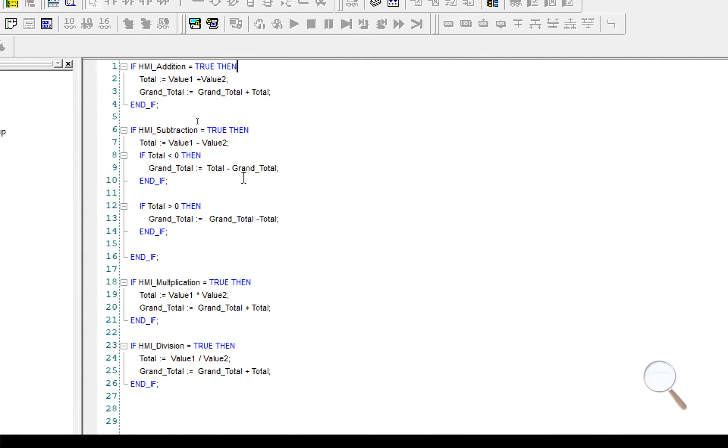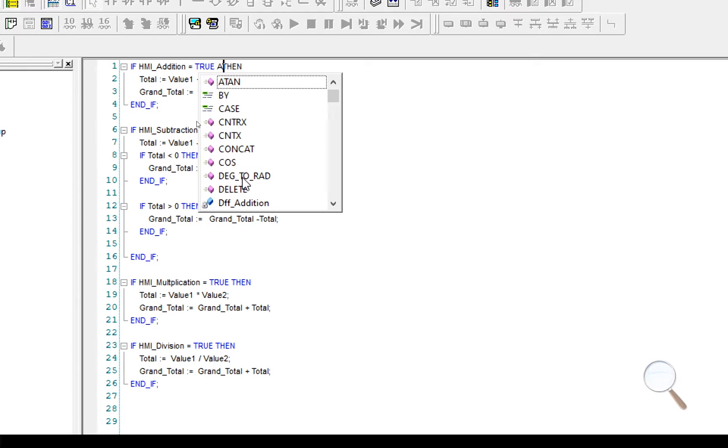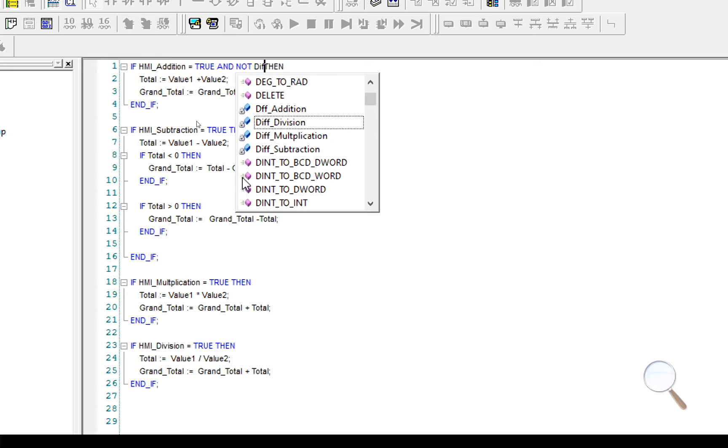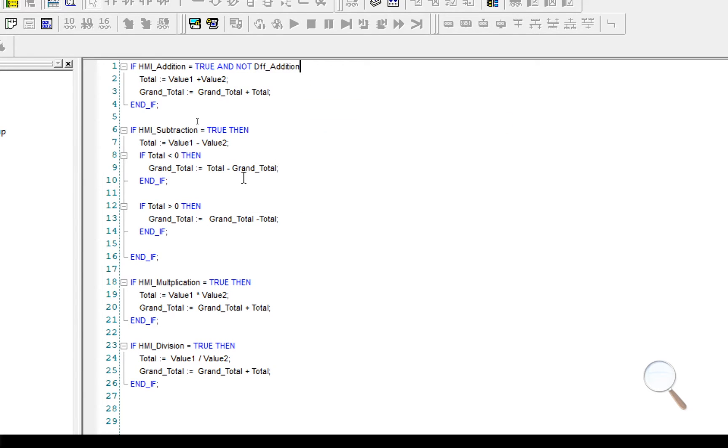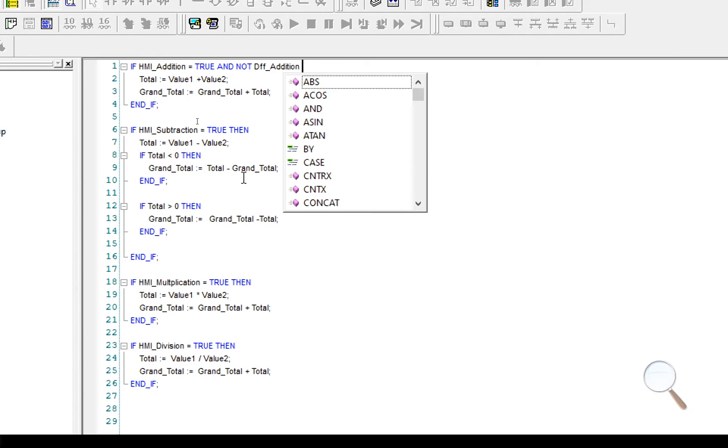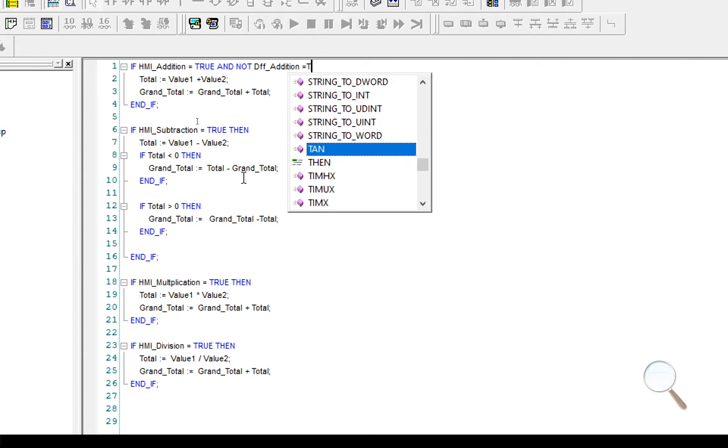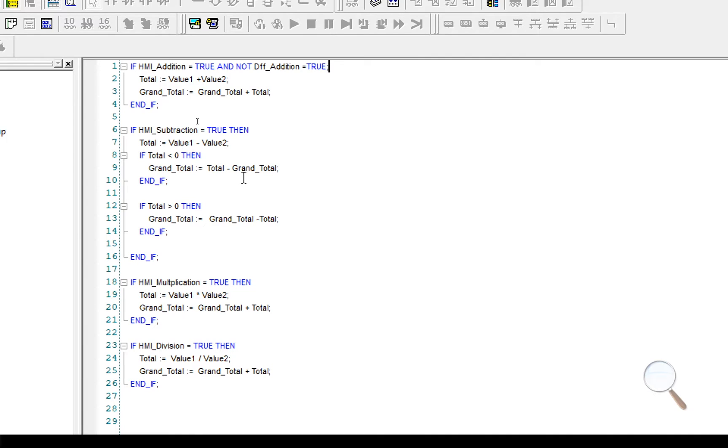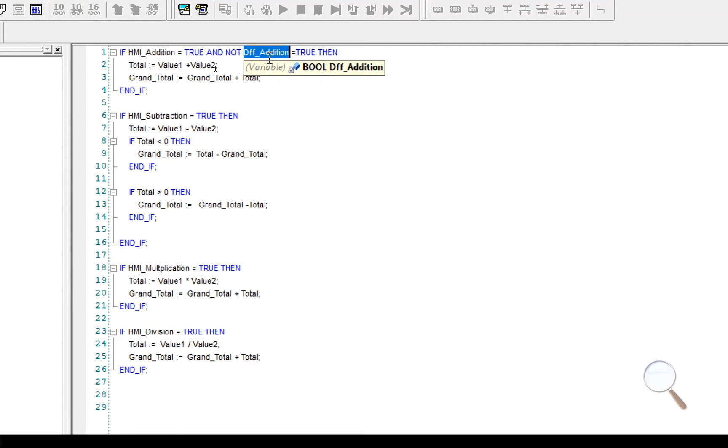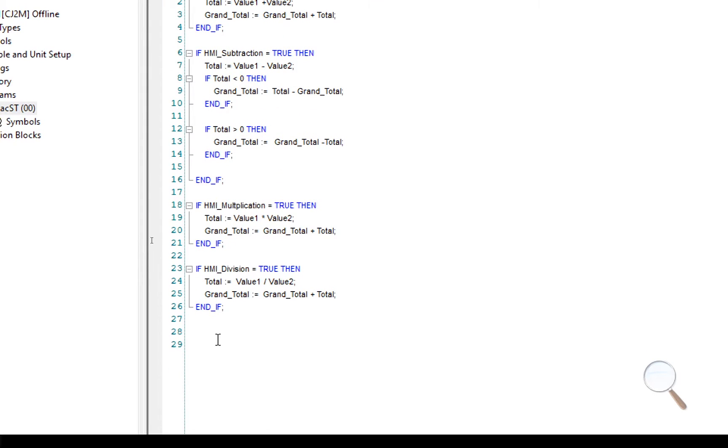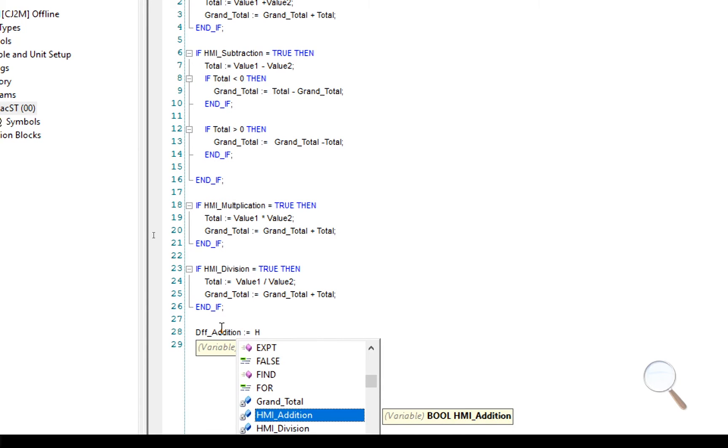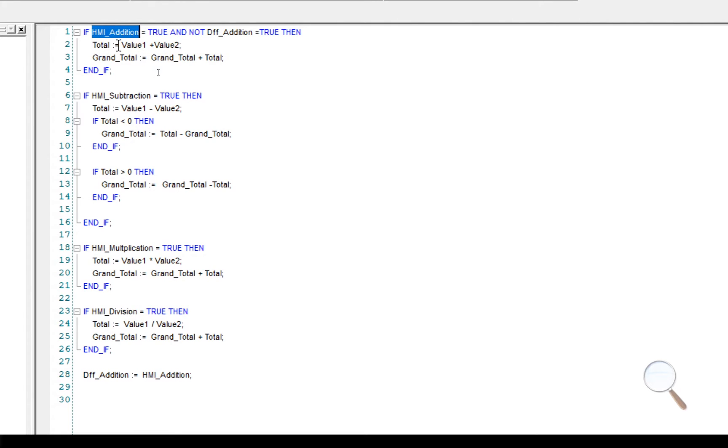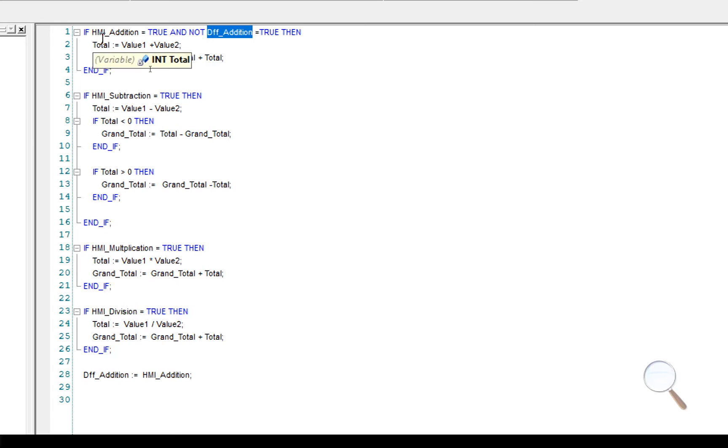I'm going to start with our addition and I'm going to add an and not. So I'm going to add diff addition to the end of my code. And I'm going to make diff addition equal to the current value of HMI addition. If you remember from previous videos, this code is going to cycle repeatedly, hundreds of times per second. When I press this button, or before I press this button, HMI addition is equal to zero. And diff addition is also equal to zero. So this code will not run because they're both equal to false.